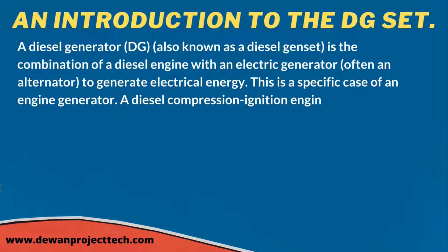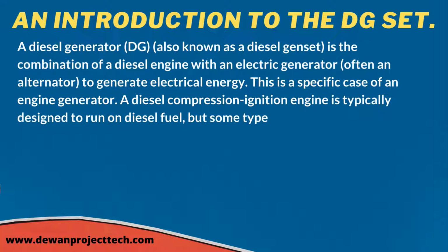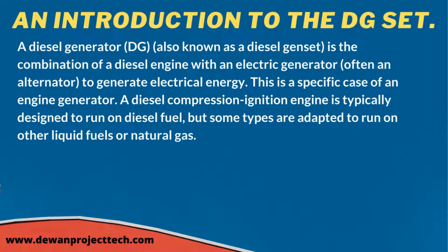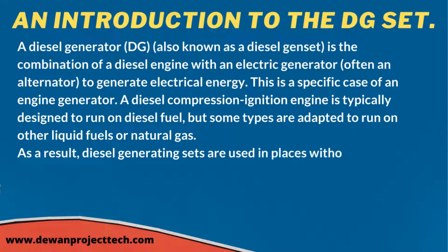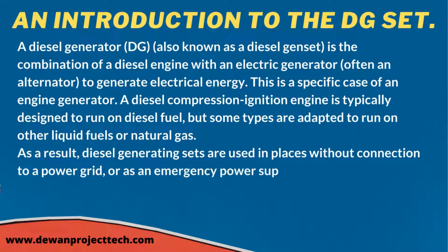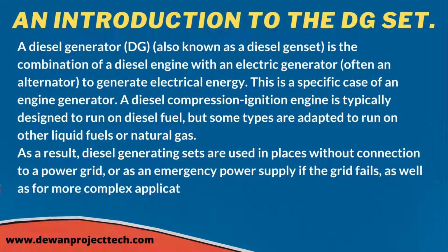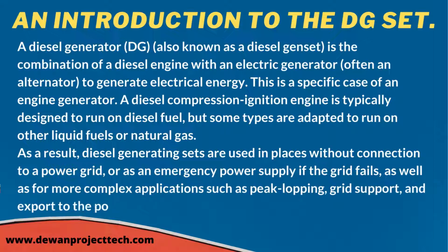A diesel compression ignition engine is typically designed to run on diesel fuel, but some types are adapted to run on other liquid fuels or natural gas. As a result, diesel generating sets are used in places without connection to a power grid, or as an emergency power supply if the grid fails, as well as for more complex applications such as peak-lopping, grid support, and export to the power grid.